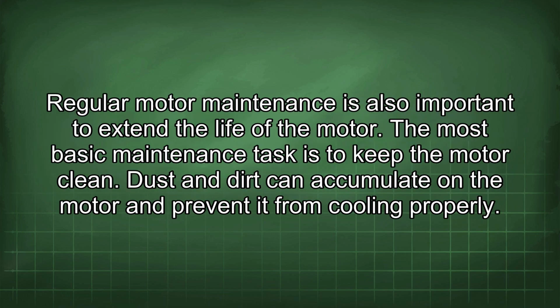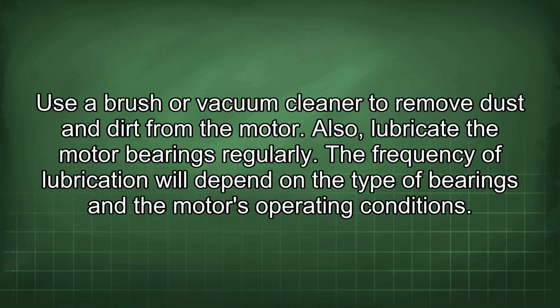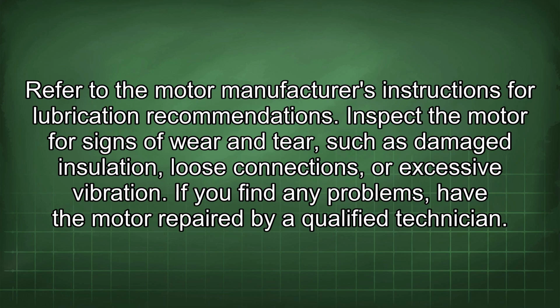Regular motor maintenance is also important to extend the life of the motor. The most basic maintenance task is to keep the motor clean. Dust and dirt can accumulate on the motor and prevent it from cooling properly. Use a brush or vacuum cleaner to remove dust and dirt from the motor. Also, lubricate the motor bearings regularly. The frequency of lubrication will depend on the type of bearings and the motor's operating conditions. Refer to the motor manufacturer's instructions for lubrication recommendations.